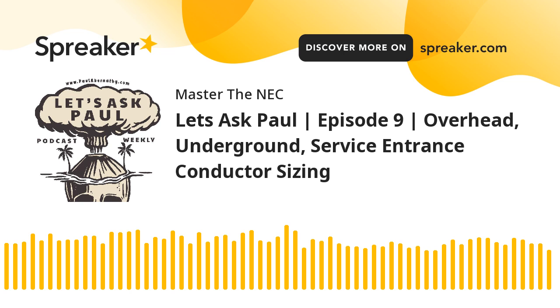Okay, so this is that allowance for you to do up to 6 service disconnects grouped in one location. And those service conductors that are coming, let's say, from the point of attachment down to, let's say, a wireway that's breaking off into these 6 different service disconnects that you're permitted to do in 230.71(B), in this case, if I added up all of the breaker ratings for these services, it probably would exceed the ampacity of these service entrance conductors, right? But this is saying, no, that's okay. That's fine, as long as you've done a calculation and you know that the calculated load is not going to exceed the amp rating of those service conductors.